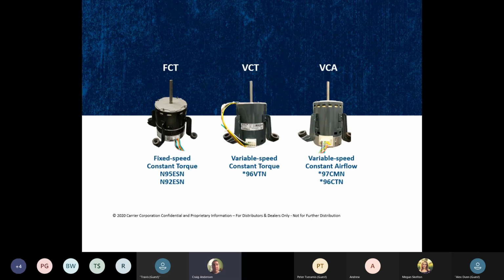So here are our motors. These are the new motors in our new units. Fixed speed, so that's our X13. We have a variable speed constant torque, which is in our 2-stage non-communicating unit. And then we have our variable speed constant airflow, which is in our 97 and 96% communicating furnace, which we'll go through. So those are the 3 motors in our new series that we need to know how to troubleshoot when we're out there.